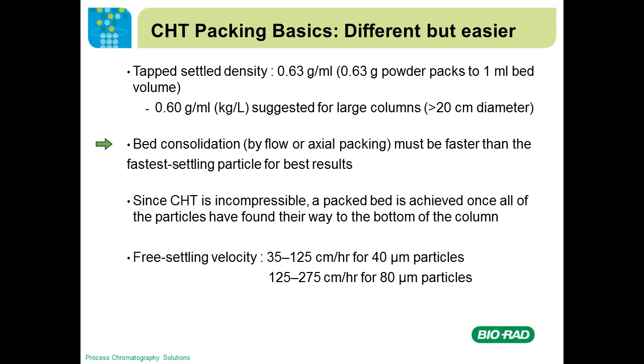Bed consolidation can be either flow or axial packing, and it just has to be faster than the fastest settling particle for best results. Since CHT is incompressible, once all particles settle to the bottom of the column, the column is packed. For 40 micron particles, the fastest settling particle is about 125 centimeters per hour, so you want to pack at 150 centimeters per hour. Packing faster than that provides no additional benefit. For 80 micron particles, however, you will need to go to 300 centimeters per hour.